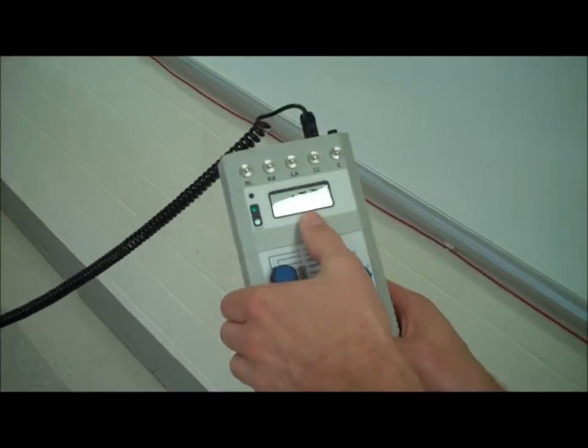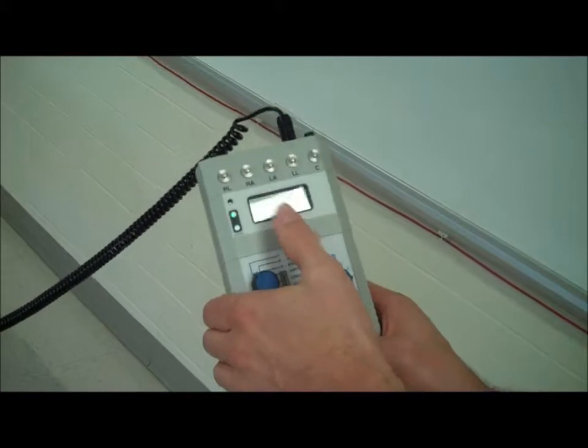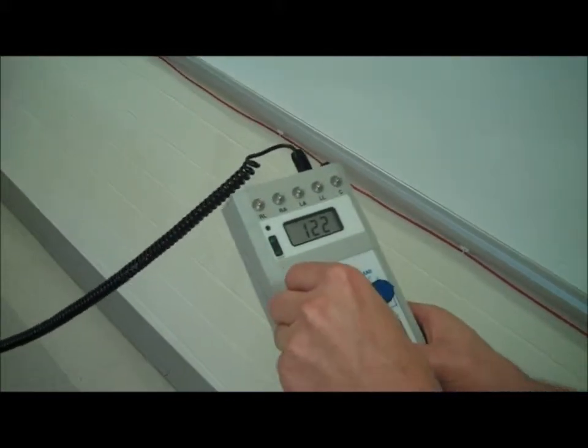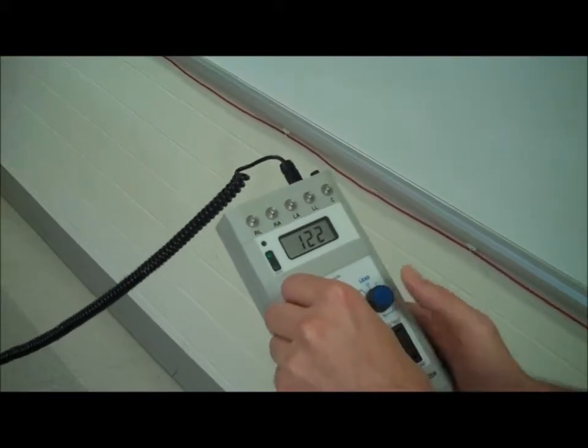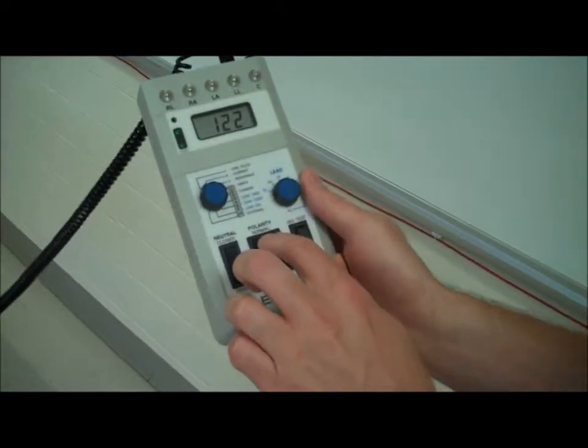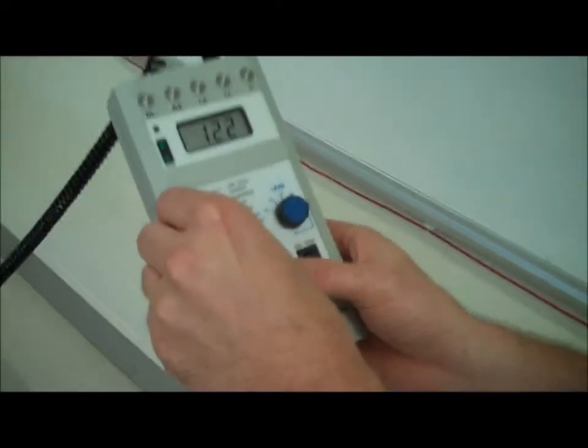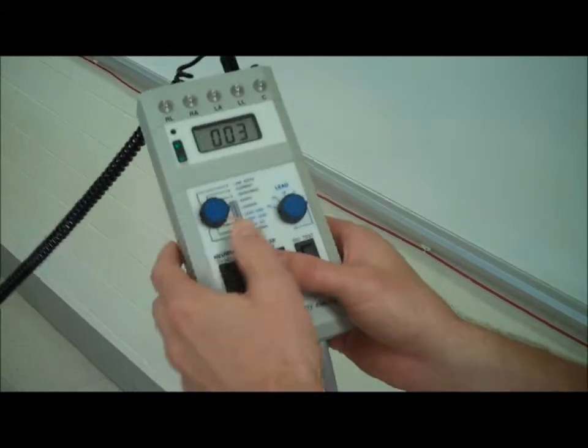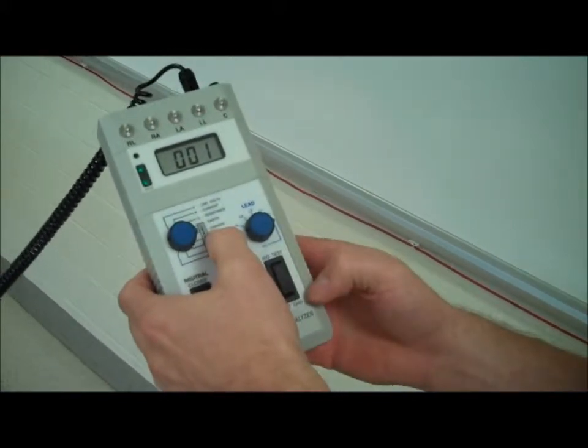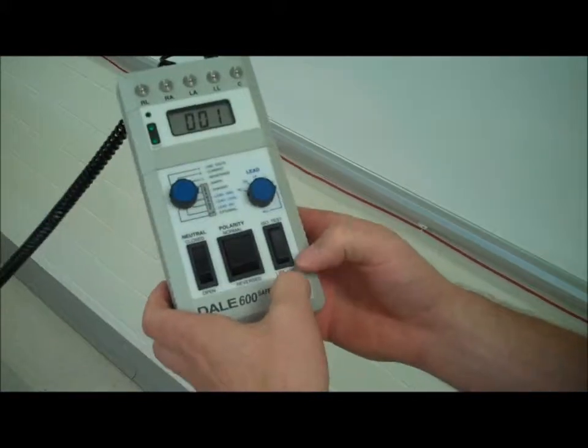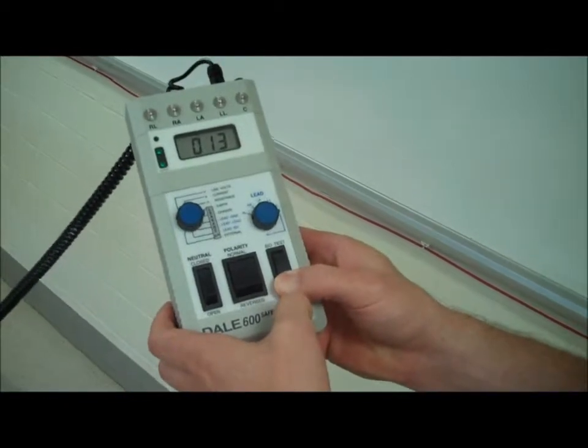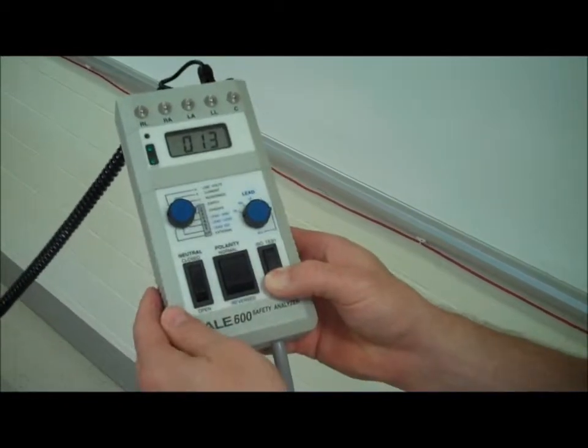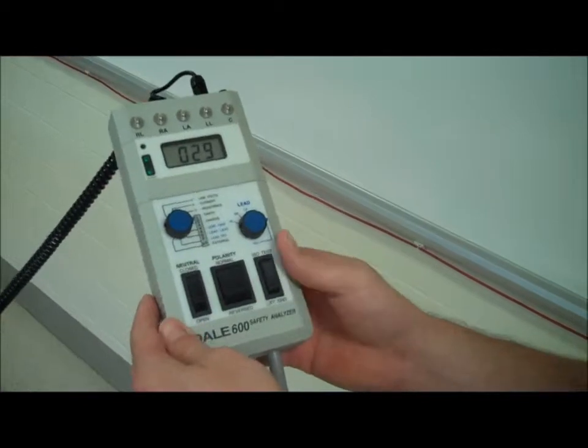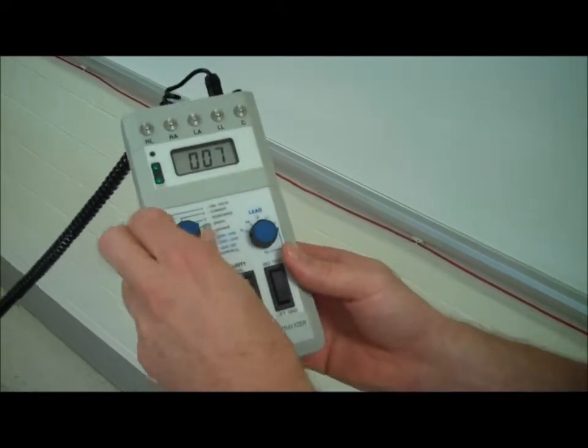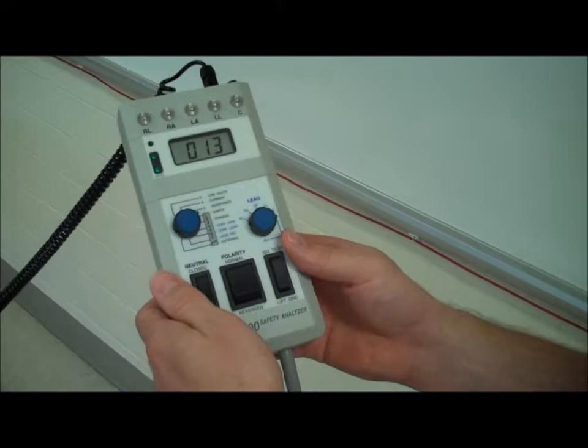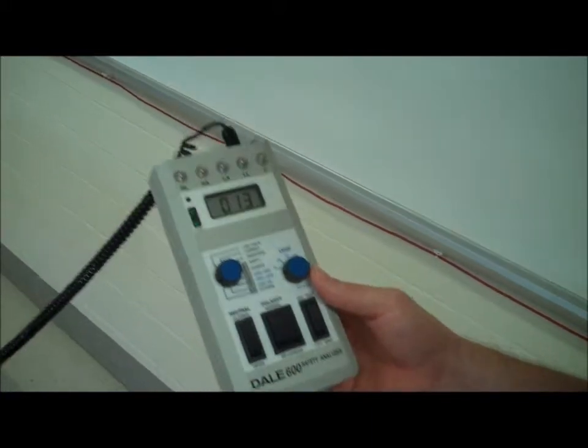We're running about 122 line volts, so we know that's good. And we'll make sure that we have it on normal. And then we're going to go ahead and switch the indicator to chassis ground. And then we're going to lift the ground. And we are within tolerance. And we're going to check earth ground. And we are within tolerance. That's good.